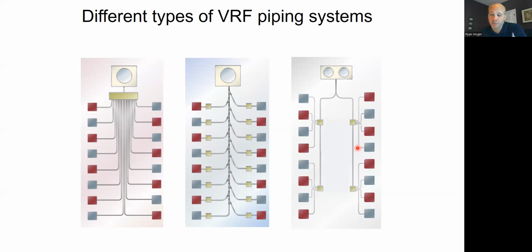Most people don't consider the piping layout when they design the building, unless it's really space constrained. They just pick the favorite manufacturer that they know how it works, and then they just make the piping work for that project. But the argument here on the left is that in many applications, you have more piping to buy, right? However, you have fewer brazing connections or flare connections if you're doing it that way. You have more piping connections over here, fewer piping connections over there. So you're trading off one thing for the other.